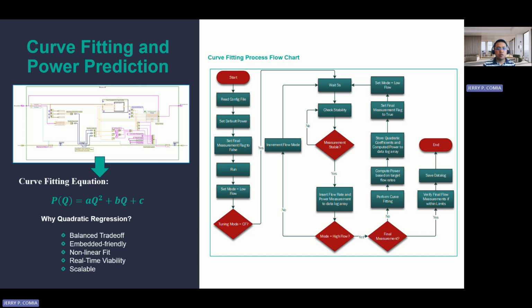The system performs the curve fitting. This step involves using three data points, one for each flow mode, low, medium, and high. These points are used to derive a unique quadratic equation for the fan. The equation is of the form P of Q is equal to A Q squared plus B Q plus C, where P is the power and Q is the airflow rate. These equations allow us to predict the required power for any given flow rate based on the three empirical data points.